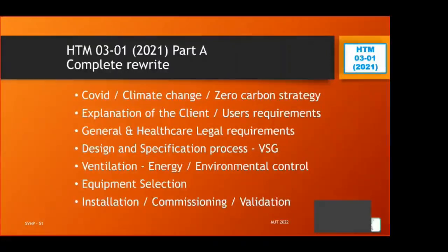The whole point about commissioning has been extensively overhauled, and so has the point about validation. Validation isn't just about agreeing the commissioning people have done their job, it's looking at the whole thing holistically and saying, does this deliver what we asked? Is it fit for purpose? Can we use it? The validator should be appointed by the client, not the installer, not the builder, not the designer. He who pays the piper calls the tune. The validator is there to look independently at what's done and make sure it's done correctly.